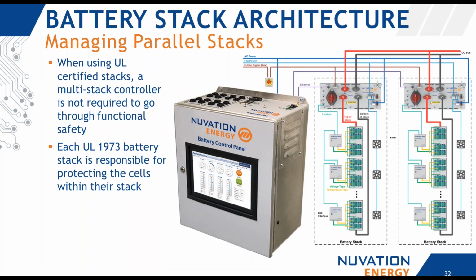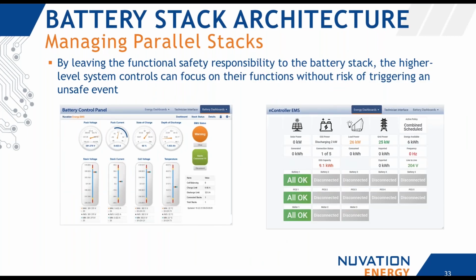Now, it's certainly helpful for higher level controls, so the multi-stack controller or energy management system controllers, to have an understanding of the safe operating range and have their own level of safeguards. But from a certification perspective, that's not required for the protection of the cells. And so by leaving the functional safety down at that lower level, these higher level systems can focus on their functions without triggering an unsafe event.